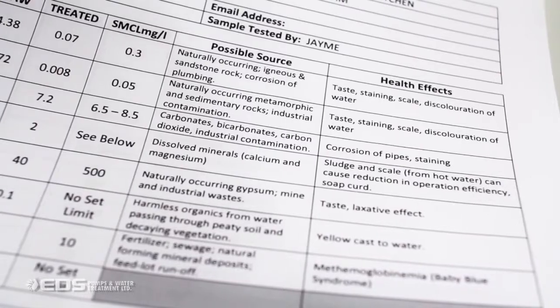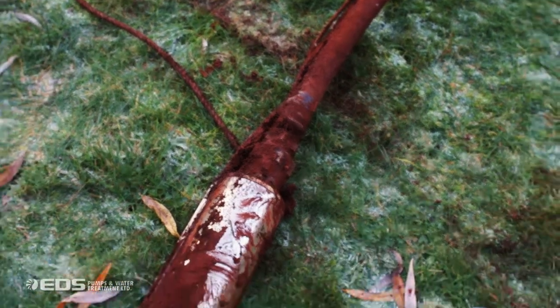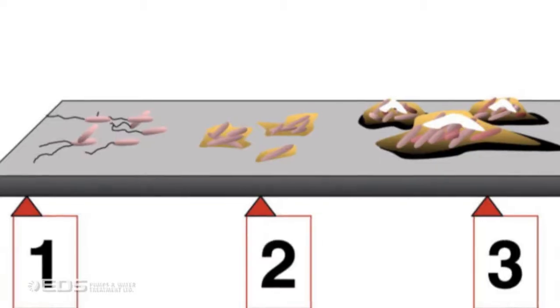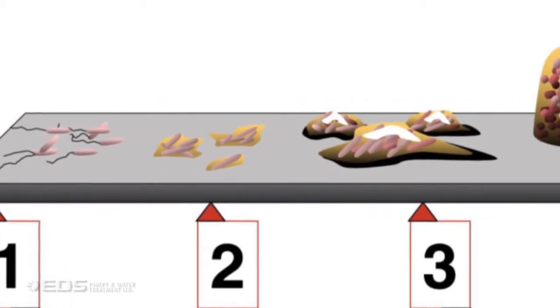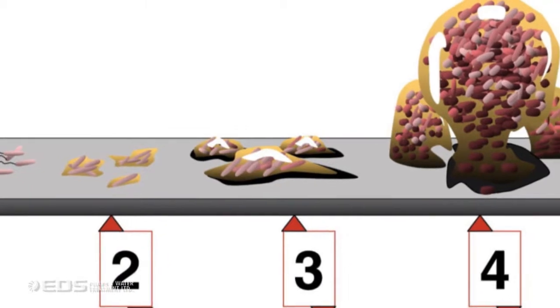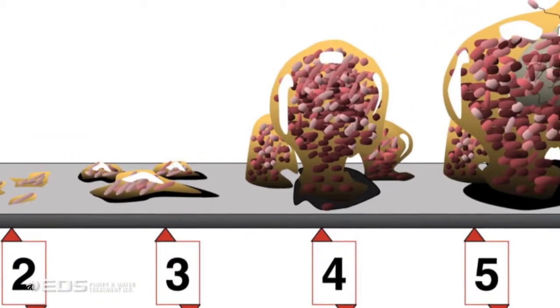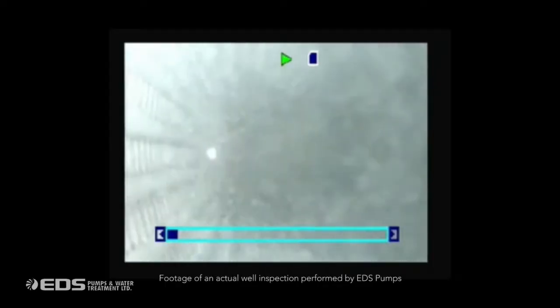The most frequent cause of well fouling is the result of bacterial growth, which can block pathways water would normally take to enter the well. Many types of bacteria form a polysaccharide film, which adheres to the well casing, well screen area, or fracture zones. This film provides an excellent means for trapping its food source, such as chemicals, minerals, and other bacteria.